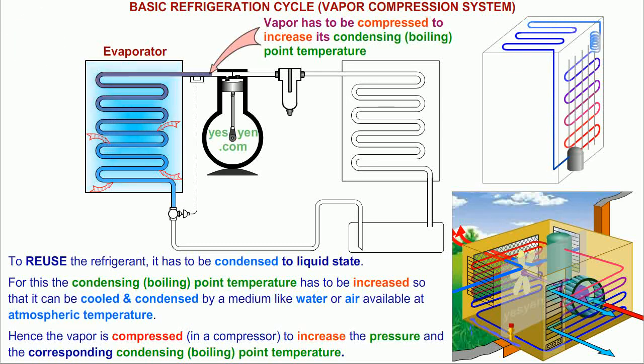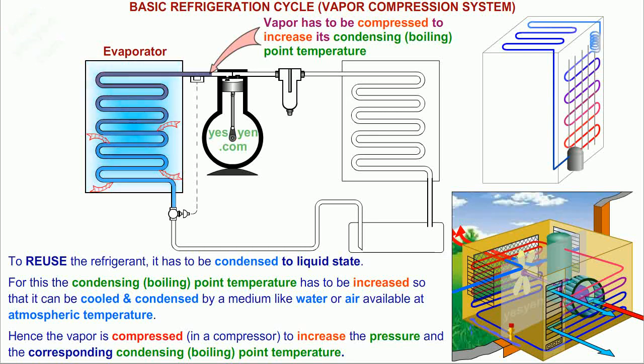To reuse the refrigerant, it has to be condensed to liquid state. For this, the condensing — that is boiling point temperature — has to be increased, so that it can be cooled and condensed by a medium like water or air available at atmospheric temperature. Hence the vapor is compressed in a compressor to increase the pressure and the corresponding condensing, that is boiling point temperature.